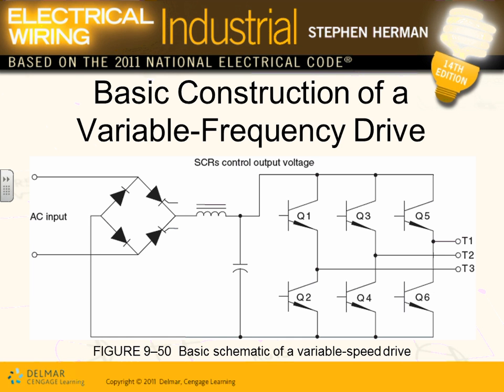You take an AC, you convert it to DC first, or some form of DC. You alter it, change it, and then you make sure that these transistors fire at different times and at different values. All electronic drive, AC drive. That's your frequency drive. When you see an AC drive, a frequency speed control, you take whatever AC you have, single or three-phase by the way, and look at that. I took single phase and I converted it to what? Three-phase. I can drive a three-phase motor from a single-phase system using a VFD. That's one of the advantages.